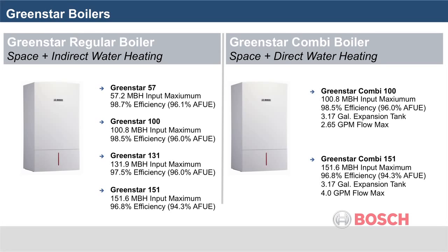The Greenstar line consists of 6 boilers, 4 of which are space heating boilers, and 2 are combi. The Greenstar regular boilers are available in 57, 100, 131 and 151,000 BTU capacities. The Greenstar combi boilers are available in 100 and 151,000 BTU capacities. Please note, the maximum domestic hot water flow at a 72-degree rise for the combi 100 is 2.65 gallons per minute and 4 gallons per minute for the combi 151. Keep this in mind when sizing these boilers.